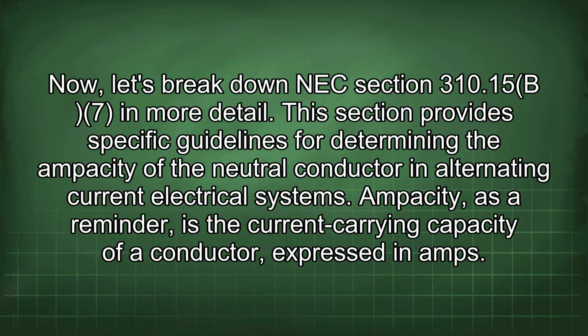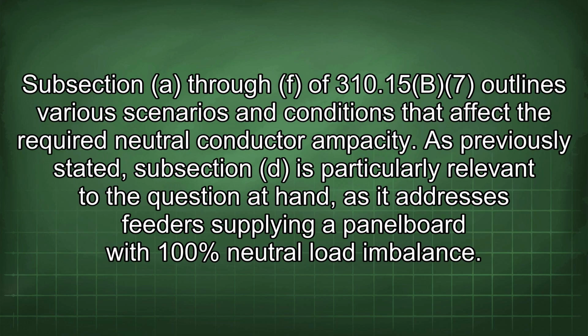Now, let's break down NEC section 310.15(B)(7) in more detail. This section provides specific guidelines for determining the ampacity of the neutral conductor in alternating current electrical systems. Ampacity, as a reminder, is the current carrying capacity of a conductor expressed in amps. Subsections A through F of 310.15(B)(7) outline various scenarios and conditions that affect the required neutral conductor ampacity. As previously stated, subsection D is particularly relevant to the question at hand, as it addresses feeders supplying a panel board with 100% neutral load imbalance.